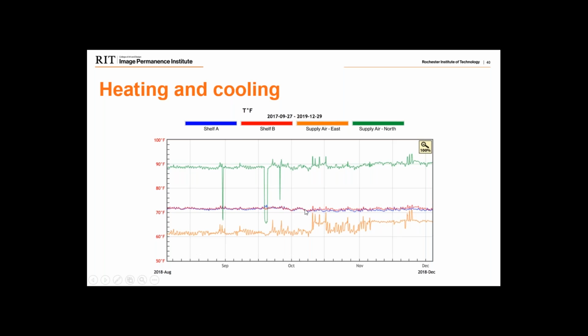Those 2 loggers, temperature-wise, completely agree with each other. They're 72 degrees and perfectly happy, almost right on top of each other. But we also have a data logger within each supply, one reading the supply from one side of the facility, one from the other. One supply was almost 90 degrees, at times 90 or more, and the other was anywhere from 60 to say 66 degrees.